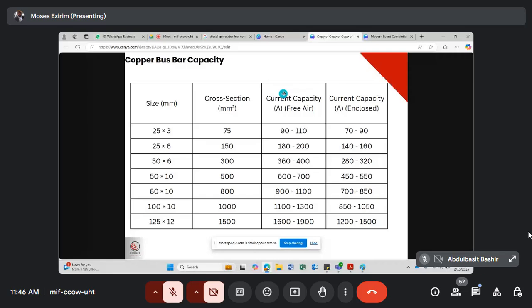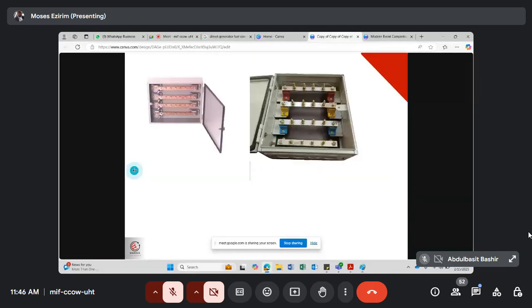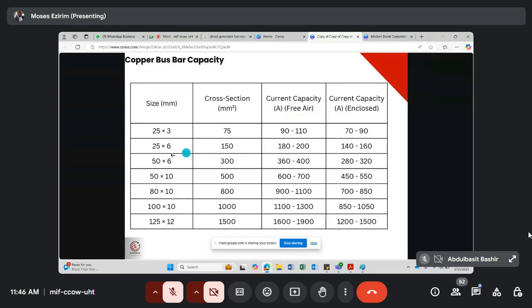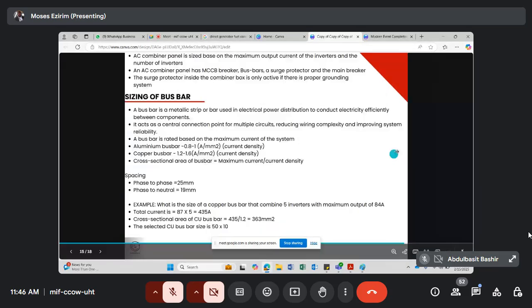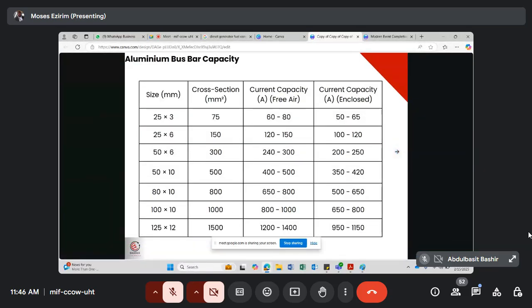If it is in free air, it means it is outside. Enclosed means it is within a box. There is a way you can bring your combiner, your bus bar, and put it outside, so you are not enclosing it. Like in this case, these ones are enclosed. All right, these ones are enclosed. So this is for copper bar and aluminum bar. So that is how to size your bus bar. So that is that for the BOS.